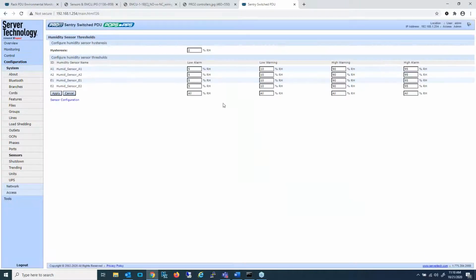We'll take a look at humidity thresholds. In this case, we find a low alarm threshold, a low warning, high warning, and high alarm. And we find also what is called a hysteresis, and that is, if a threshold is exceeded, it needs to return to that threshold and that much beyond in order for the alert to clear.